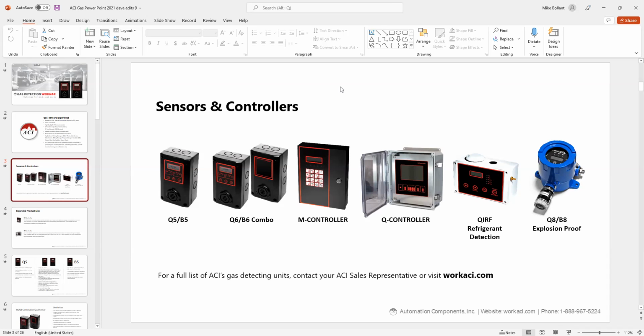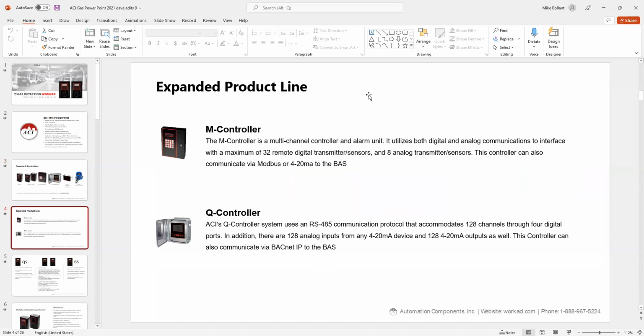The next sensor is our QIRF, which will be our Freon detection sensor. It's infrared technology, and I'll touch base on that on the other PowerPoint and get in depth on that. And then, of course, our Q8 explosion-proof sensors, and the B8, which is just the BACnet version of it. I'll talk about the features as we go on. Like I said, here's the M controller and Q controller, RS-485 communication. They can be 4 to 20, however you want to do it, Modbus. And the Q controller is the only version right now that you can do a BACnet IP if you need to interface back to your BAS via that communication.